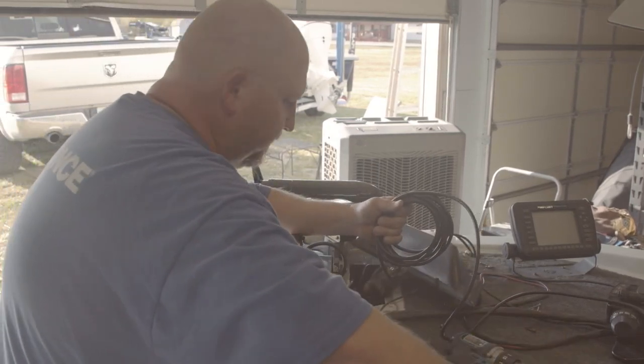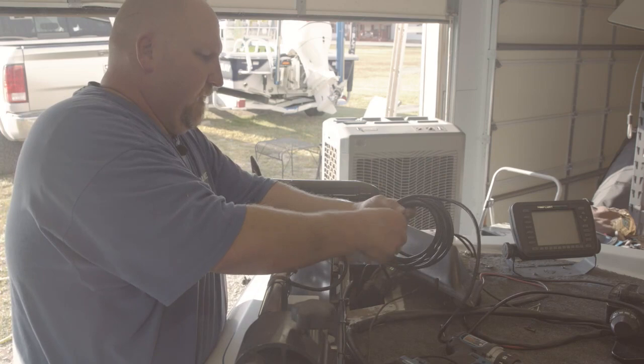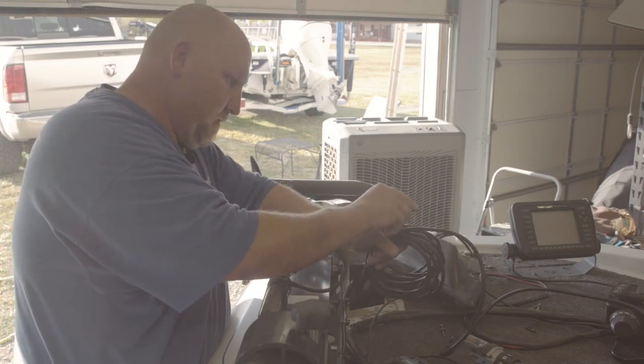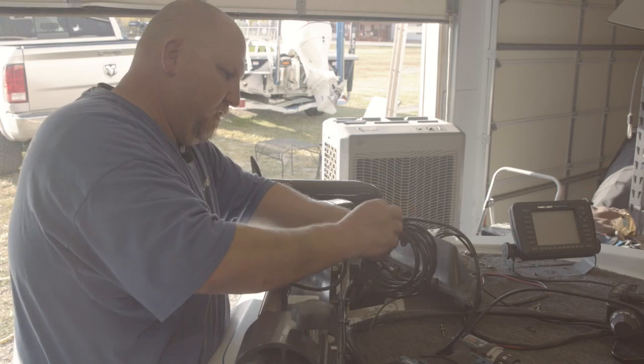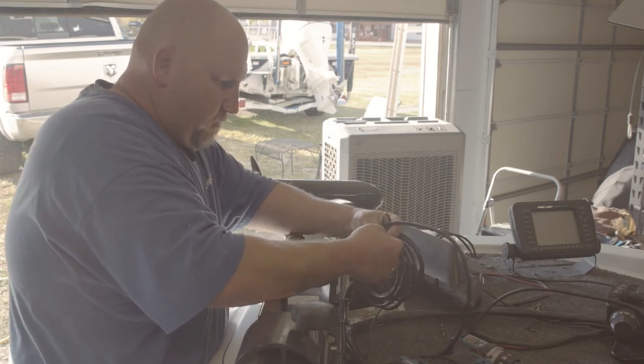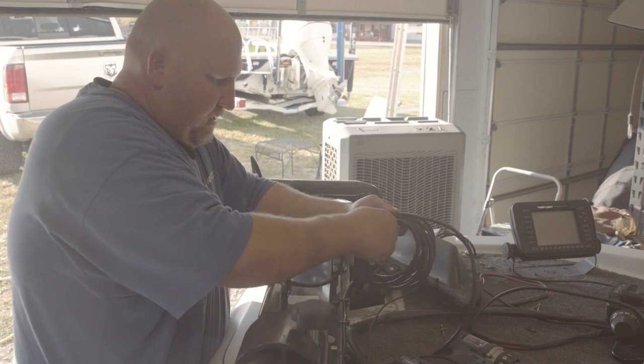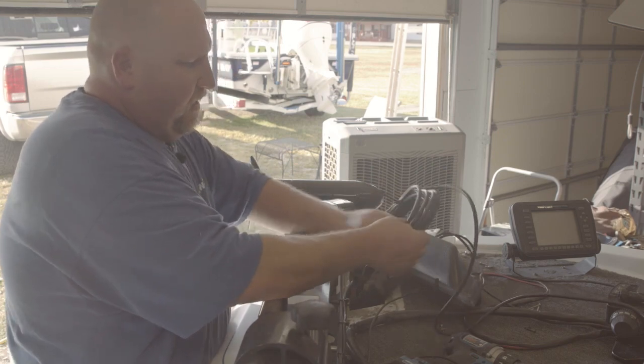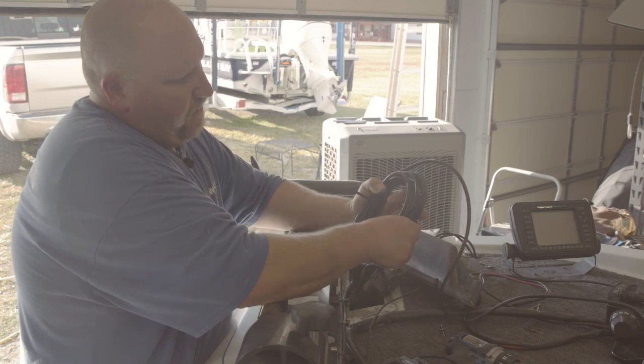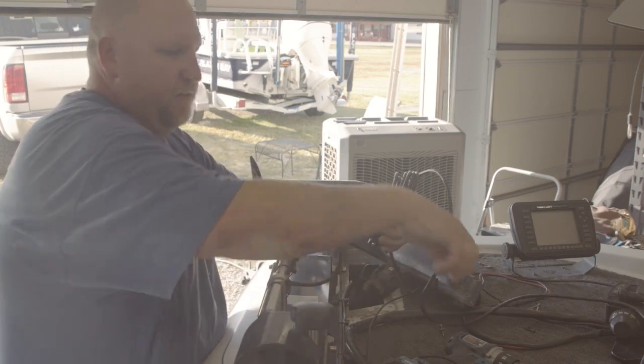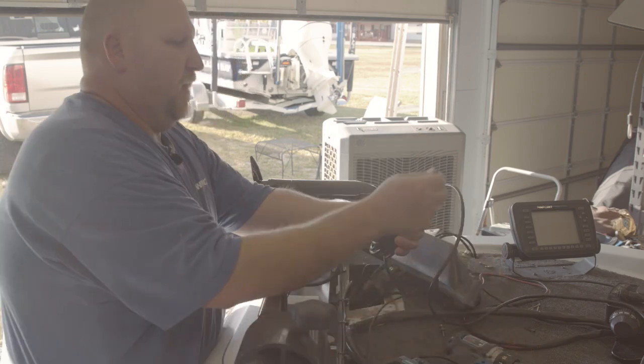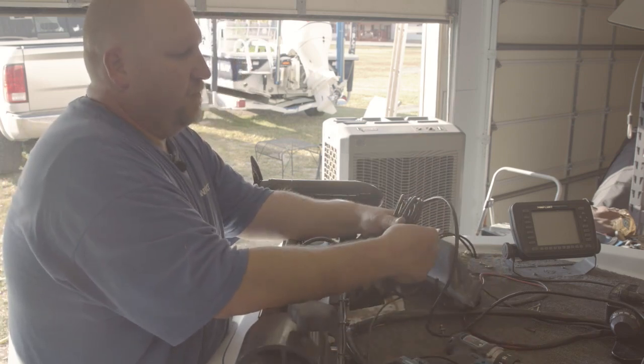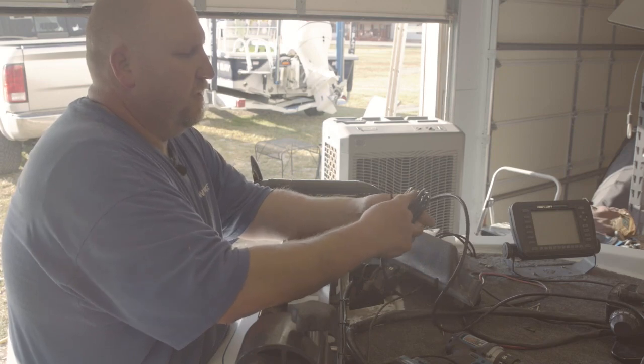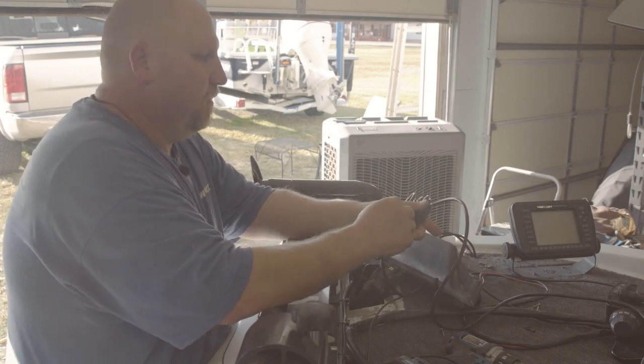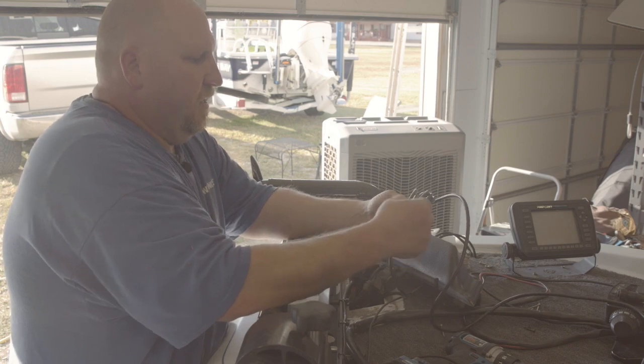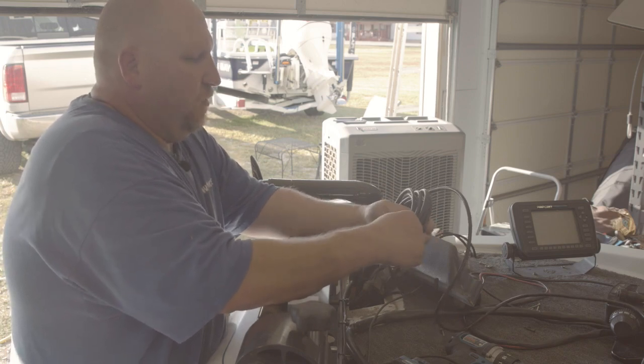Now that I've made these nice tight coils, I'm going to take two zip ties and do one on each side of it, just to make it a little cleaner. A lot of guys will take their cables and bunch them together and squeeze them really tight. I don't like to do that with transducer cables and Ethernet cables, because if you bend them too much, there's a chance of creating too much of a bend and causing the wires inside to break.